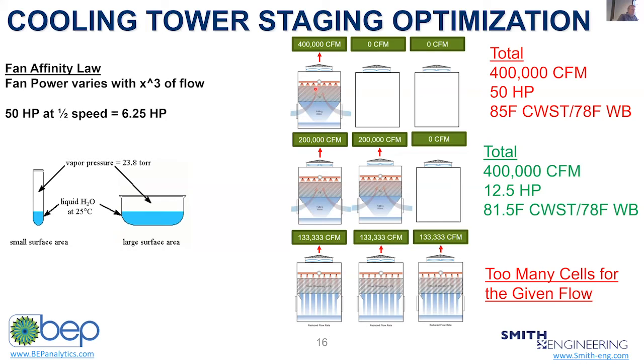I'm going to give an example here where we're running 1 tower at 400,000 CFM. We turn on 2 towers at the exact same operating conditions, and that means I can spread the 400,000 CFM out over the 2 towers. The cooling tower is the single piece of equipment in HVAC that actually follows affinity law. At 0 flow, I have 0 differential pressure, which has 0 horsepower, if it could go down to a minimum speed of 0, which it can't. But in all other systems, I'm holding a minimum differential pressure or some type of set point, so there's never a 0, 0 XY intercept, whereas this has a 0, 0 XY intercept. So the cooling tower follows affinity law very well.